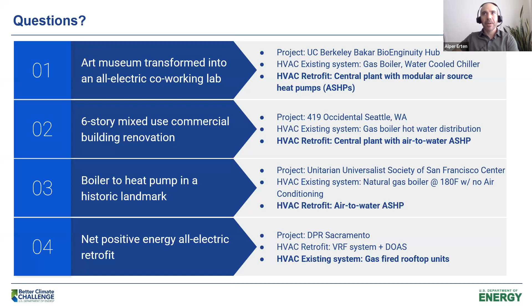Heating, as Stet already talked about, you can't go above about 110 in general, or it's not advised to. So for our location, we didn't have any issues because the outdoor temperature doesn't get that cold in the Bay Area. If you were in colder climates, what we usually do in projects with electric central plants is either keep the existing boilers as backup, or suggest electric resistance backup heating, or geo loops for wintertime backup, or thermal storage.